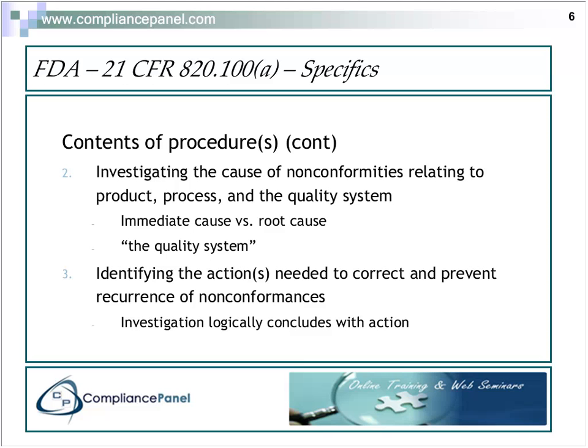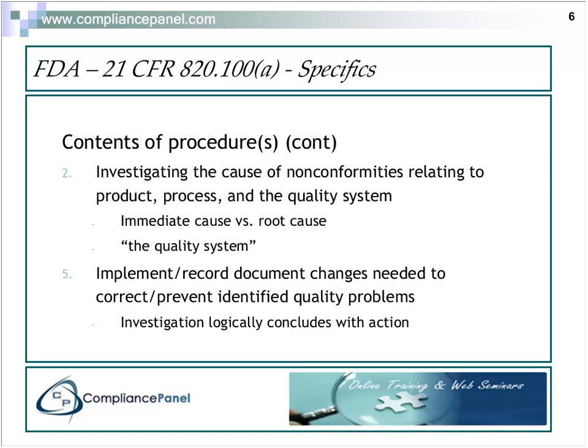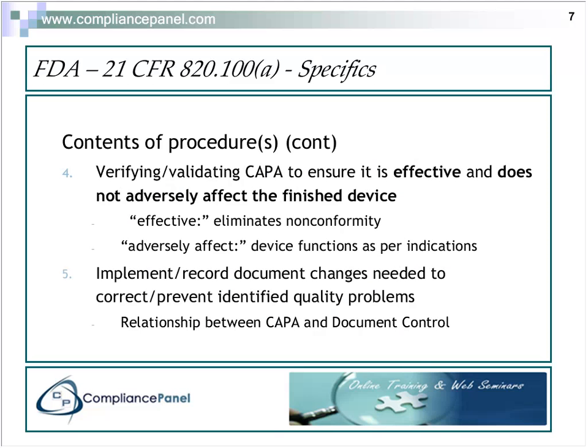The procedure also requires you to identify the actions needed to correct and prevent recurrence of nonconformities. Investigation logically concludes with action. I like to state that during my presentation. And the question here is, how does the investigation that you've done show that the action that you're going to implement is the correct or logical one? By verification or validation.